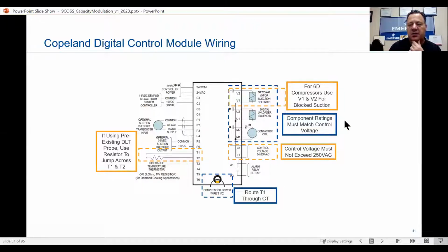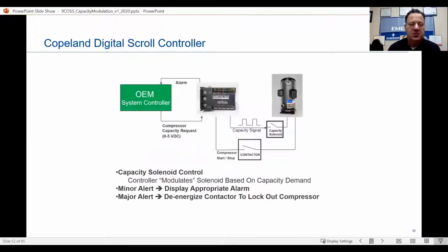Some of the other things here, for the 6D compressors, use V1 and V2 for a blocked suction, okay? And the V1-2, this is for vapor injection solenoid. I'm not going to really get into vapor or liquid injection, but that'll be for another day. So how that works with the open loop Copeland digital scroll controller, we have the OEM system controller. We start off at the set point, comes back through the IDCM. The contactor pulls in. We send out the IDCM. I'm in trouble saying that today. It sends out the capacity signal to the scroll compressor, to the digital, okay?